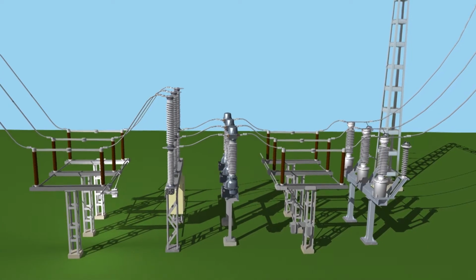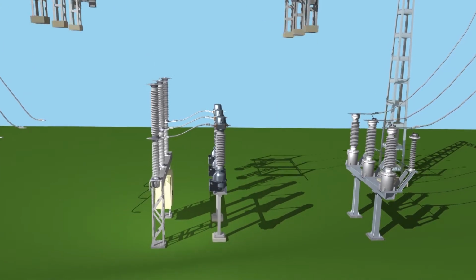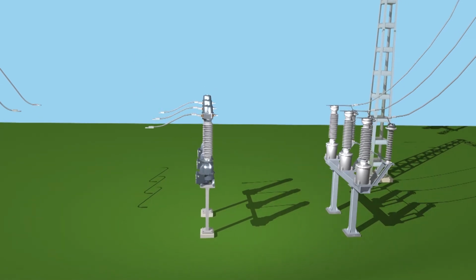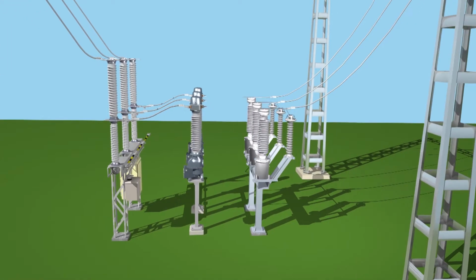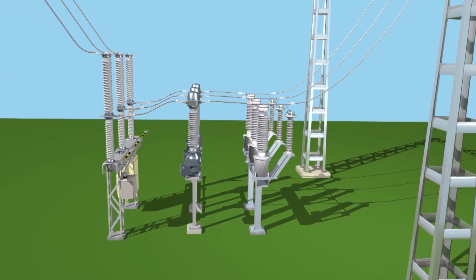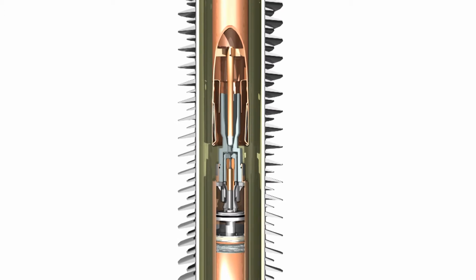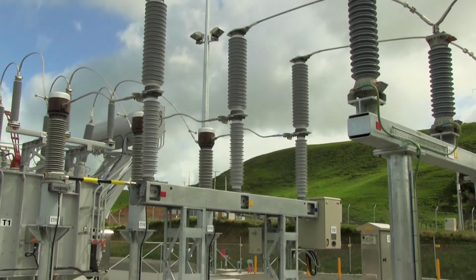The solution for Transpower would be to eliminate the disconnectors and install ABB's disconnecting circuit breaker, DCB. The disconnecting function is integrated into the breaking chamber and is completely protected from the elements. No separate disconnectors are needed.